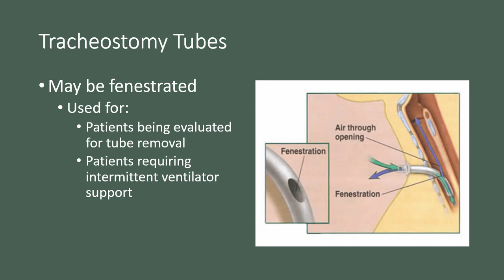remember that with the tracheostomy tubes and also with a lot of these other medical devices, if these patients are calling 911 in reference to an issue with that, they've already tried all the troubleshooting that they know. So in a lot of cases, the main thing they need us to do is supportive care and get them to the hospital. For troubleshooting, you'll follow the DOPE acronym. You want to check the device. Is it dislodged, displaced, or disconnected in the case of artificial ventilation?